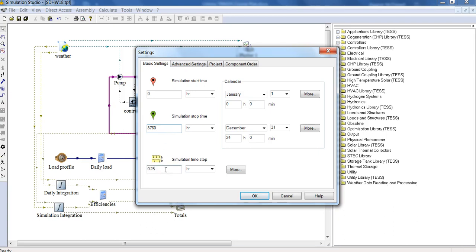Then we have the simulation time step. For running annual simulations quickly, just to get a rough idea, you set a more coarse time step, 0.25 or sometimes even one hour. But if you set this time step too coarse, it won't give you realistic results at all. When you're running proper simulations, you might even want to do it as fine as 0.02 or 0.01 hours, depending on what you're simulating.